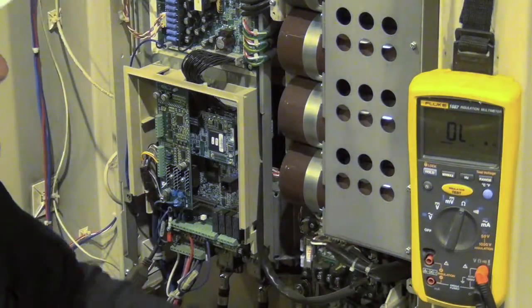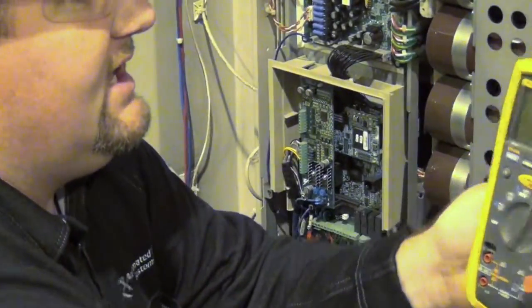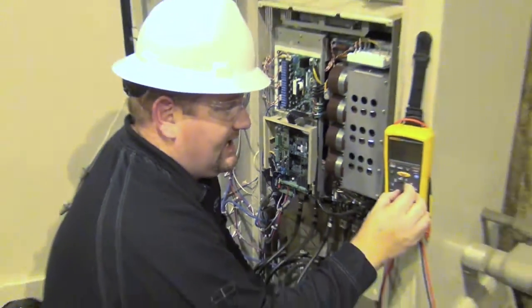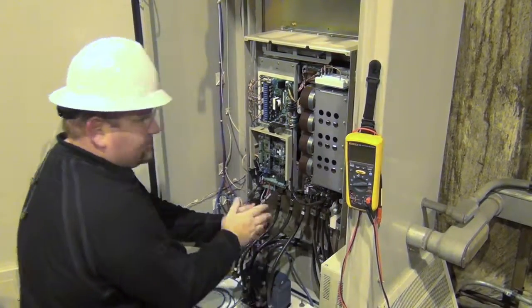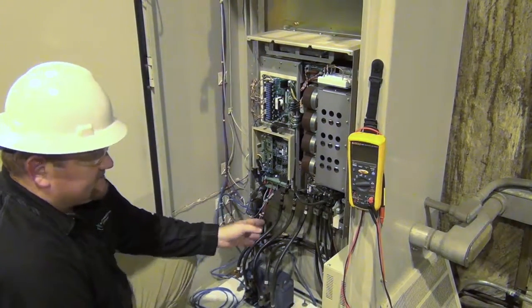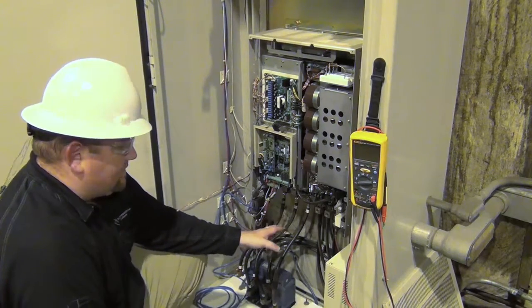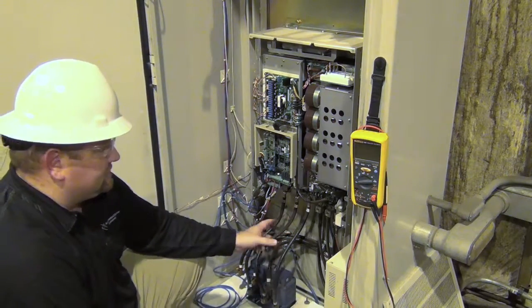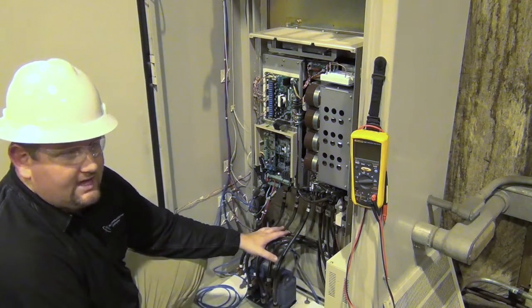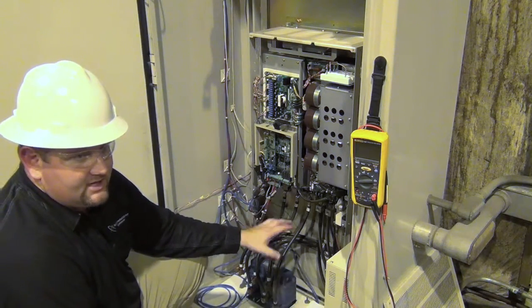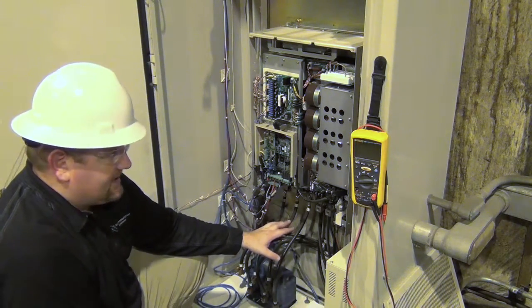So on this portion of the test, sometimes people will take an ohm reading from line to line. On the motor side, generally, especially if it's a Y-connected motor, the motor will actually appear with an ohm test as a direct short. And that is okay. That's how a motor is designed to work. Again, it's not something you should be alarmed at if you take that measurement.